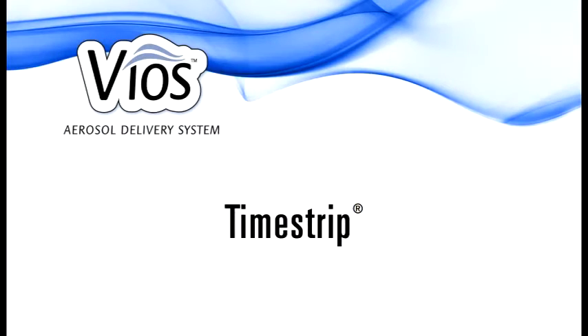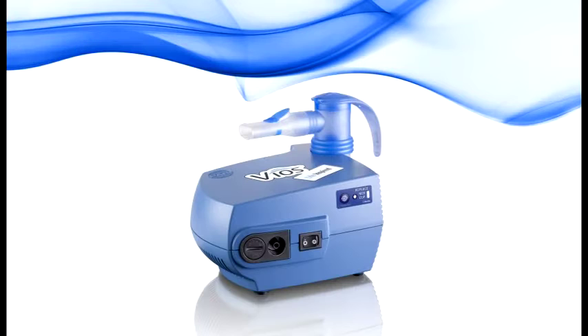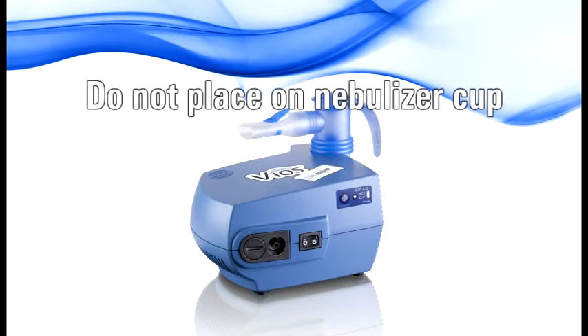It's really important to replace your PARI reusable nebulizer every six months and we want to make it easy for you. Included in your nebulizer pack is a Timestrip. To activate, squeeze the bubble on the top of the Timestrip. A red line will appear in the small circle within one to two minutes indicating activation. If you do not see the red line after three minutes, press the bubble again. Remove the adhesive tape on the back of the Timestrip and attach the Timestrip to the front of your compressor. Do not place the Timestrip on your nebulizer cup.